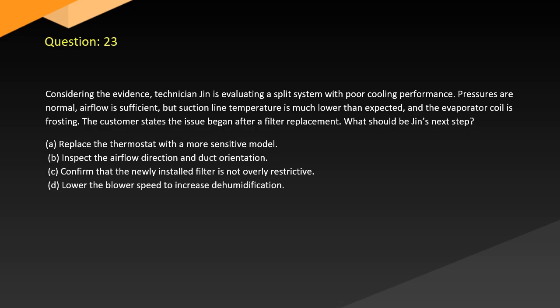Question 23. Considering the evidence, technician Jin is evaluating a split system with poor cooling performance. Pressures are normal, airflow is sufficient, but suction line temperature is much lower than expected and the evaporator coil is frosting. The customer states the issue began after a filter replacement. What should be Jin's next step? A. Replace the thermostat with a more sensitive model. B. Inspect the airflow direction and duct orientation. C. Confirm that the newly installed filter is not overly restrictive. D. Lower the blower speed to increase dehumidification.